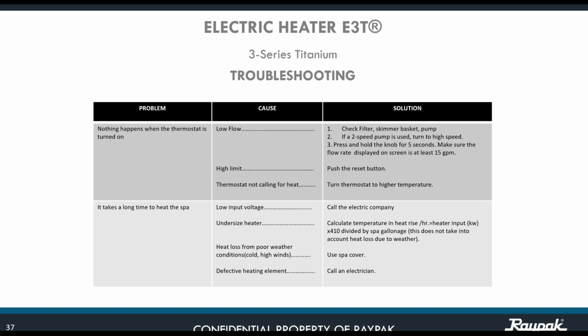That's the reason why the next cause of that particular situation is heat loss from poor weather conditions, such as when it's cold outside or there is a high wind, so you need to use a spa cover. Also, why might it take a long time to heat the spa? You have a defective heating element. Please forget about that, call an electrician. You need to call us. You need to call Raypak, and we're going to refer you to our proper warranty station to take care of the situation. Perhaps the condition is not related to the unit itself but to an external situation. If you have a defective heating element caused by an excess of acid, which we're going to see in the next slide, then that is a different situation.